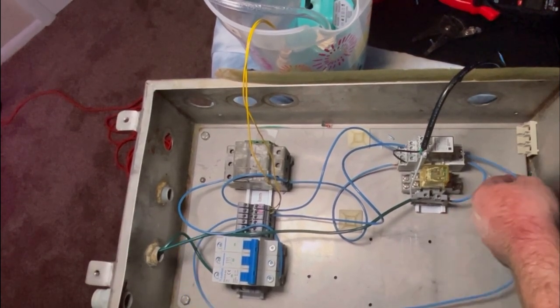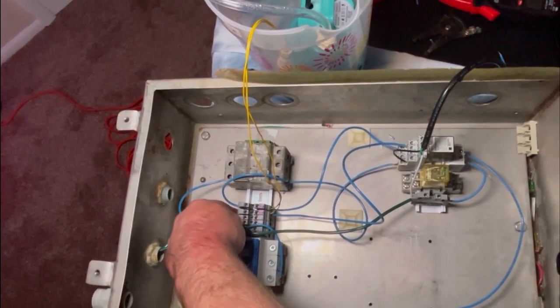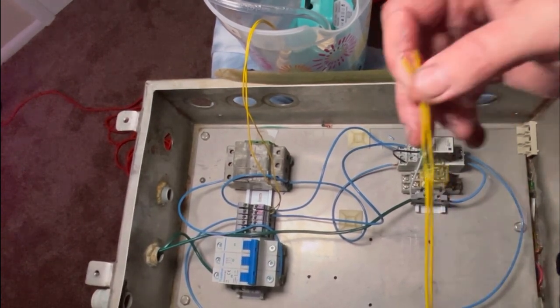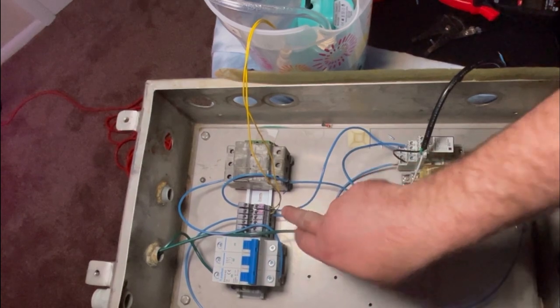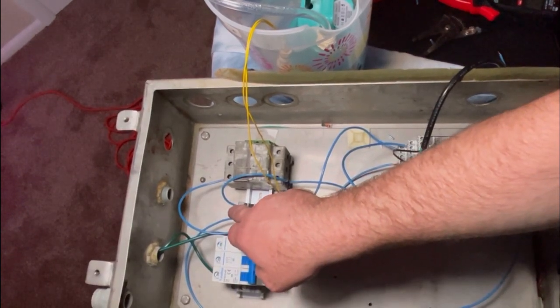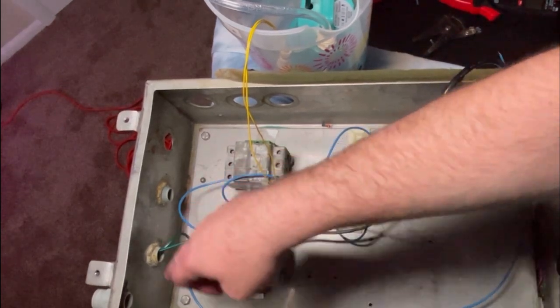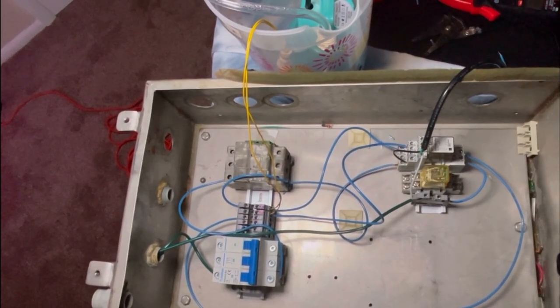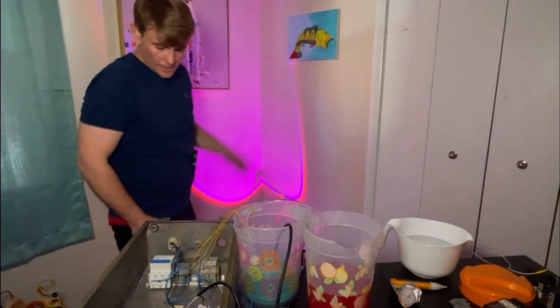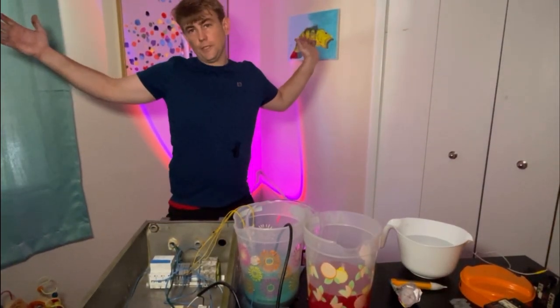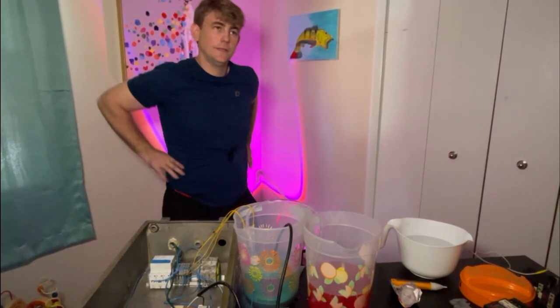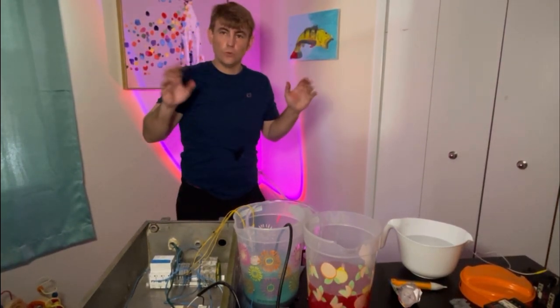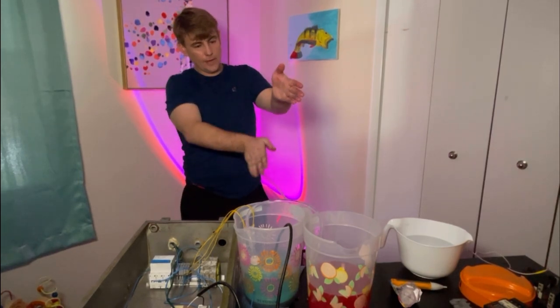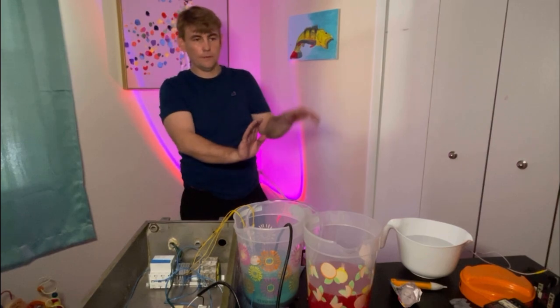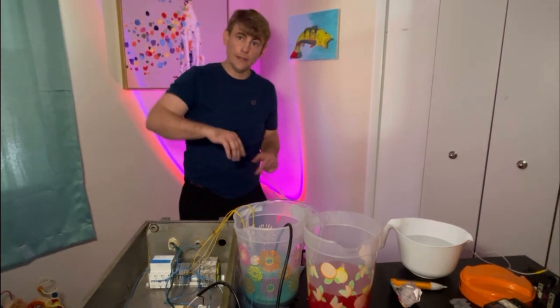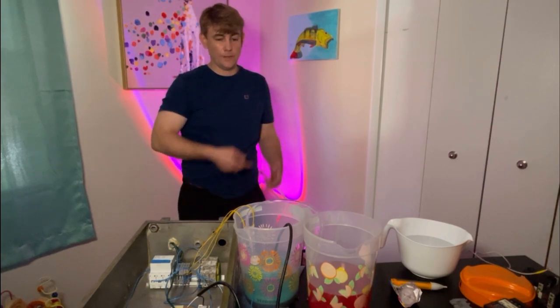All right. So I took off the wire that feeds the relay. I moved over one terminal. And again, we just said we're going to interject this float switch in series. So after that parallel circuit, it's going to come out, go through this float switch, back over here and back to the relay. I'm going to wire that up and we're going to test it. Installed our parallel latching relay contact, and we installed a low level switch, normally open. It's going to hang down here and it's going to be made, a closed circuit. So basically we don't even have to worry about it. But once the tank gets low, it's going to interrupt the circuit and the cycle is going to start again.